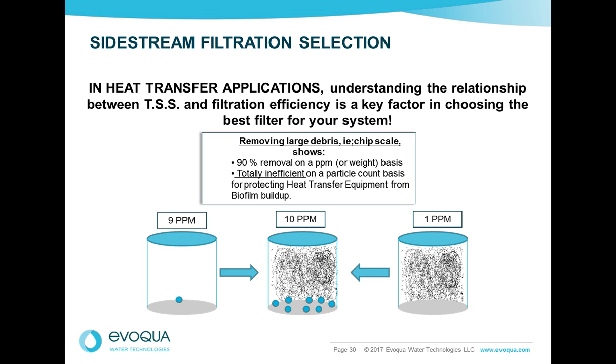You can see on this graphic on the bottom of the page, 9 ppm of a large particle is really not the same as 1 ppm of a bunch of small ones. You've got billions of those small ones that are going to start sticking. So before you choose a filter, remember to review the volume and the counts to have a clear picture of your conditions.